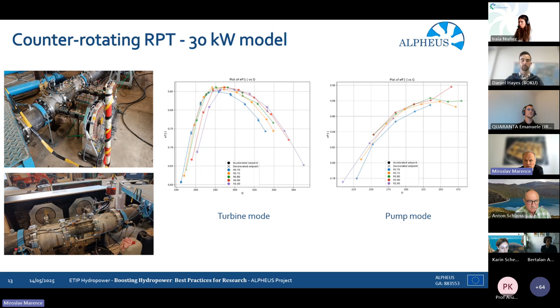This makes the system attractive, especially if we look at the setup, in which we have very short power waterways on both sides, just intake and outlet structures after the turbines. Then these hydraulic friction losses can be minimized, and in this way a full cycle efficiency of approximately 70 plus percent could be achieved. The powerhouse design was done on an ideal level, you can say, but here you see the sea outside, the reservoir inside, just the short intake part, the turbine, and a similar system like we use, for example, in bulb turbines in standard hydropower.